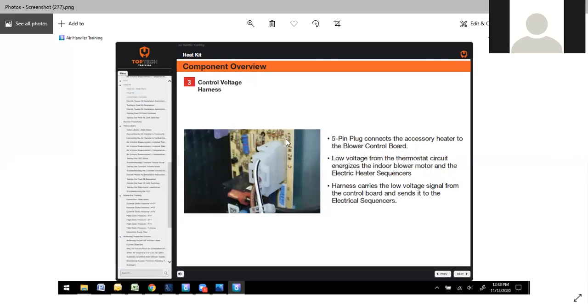This is your control voltage harness. 5-pin connector connects to the board. Low voltage energizes from the thermostat circuit, will energize your blower motor and the sequencers. The harness carries the low voltage signal from the control board and sends it directly to the sequencers.